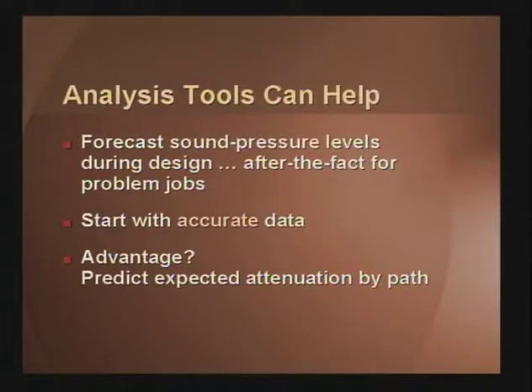These analysis tools can help at several phases during the job. It can forecast sound pressure levels during the design process when it's easy to make changes and cost optimize the system. Or it can be done after the fact if you have a problem job, because identifying a noisy path on a real job by just simply measuring it is very difficult to do. On all of these analysis tools, you need to start with accurate sound data of the source. Remember, garbage in, garbage out.